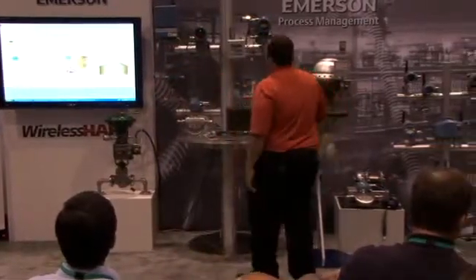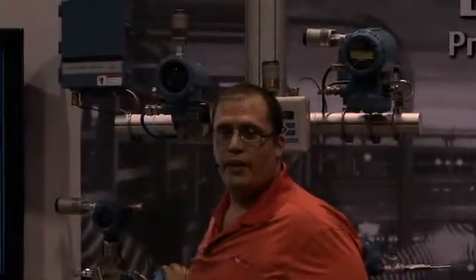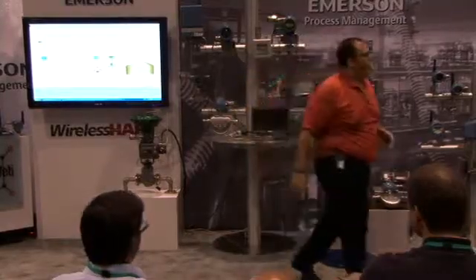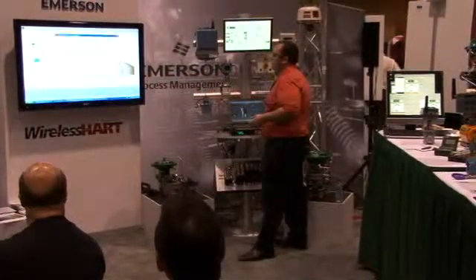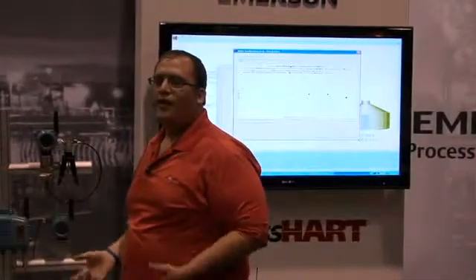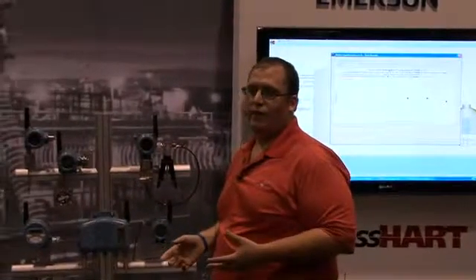Another big example is a Micromotion Coriolis transmitter. One of the things done all the time is meter verification — often it's part of a maintenance routine. If this is being used for custody transfer, you need to maintain that documentation. With wireless, using the THUM and AMS, we can do all that automatically. We can see on this screen that through the THUM we can do all our meter verifications as well. It takes a lot off your maintenance, automates the process, so you can focus on solving real problems instead of documentation.